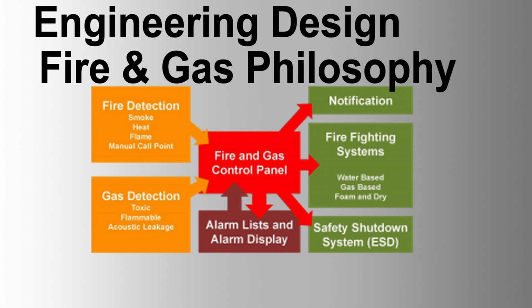Major functions. The fire and gas system operates independently to detect hydrocarbon, toxic gas leaks, and any type of fire, perform alarm and shutdown logic, automatically initiate shutdowns, open deluge valves, close fire dampers, and trip electrical feeders. Activate emergency depressurization and ESD2 level shutdowns for confirmed fire. Activate flashing beacons, fire and gas alarms via PAGA systems. Record data for sequence of events and generate DCS alarms to alert operators. Provide startup permissives and activate mimic panels. Activate extinguishing systems.